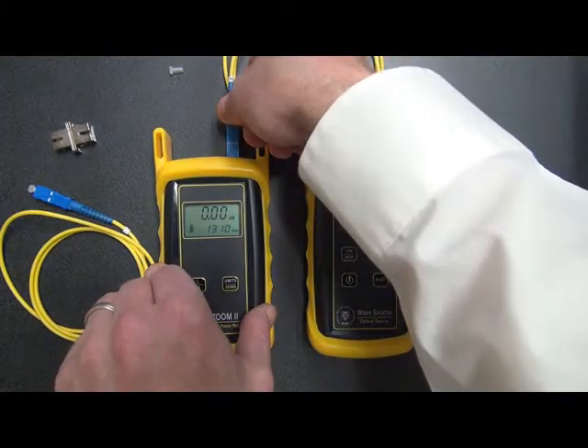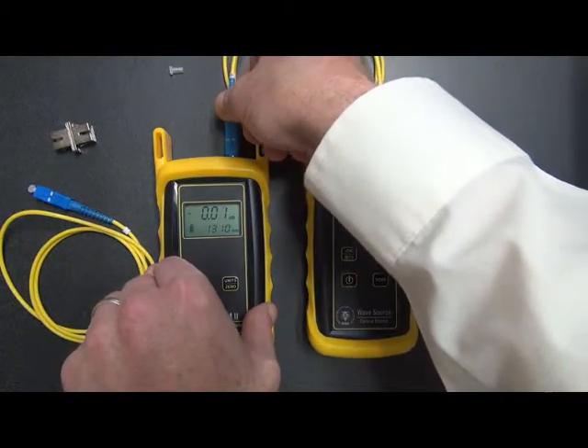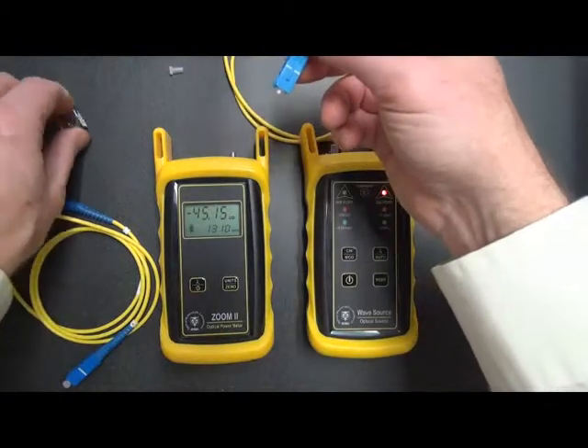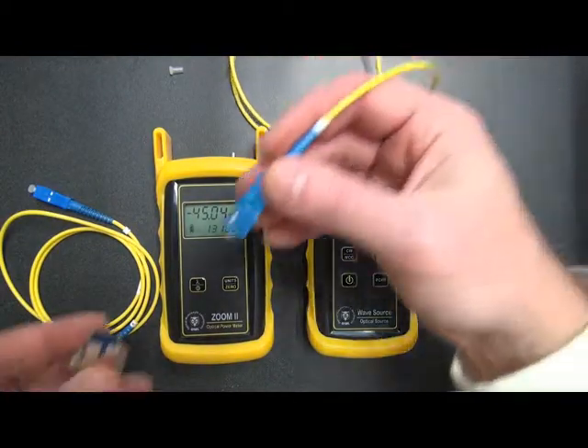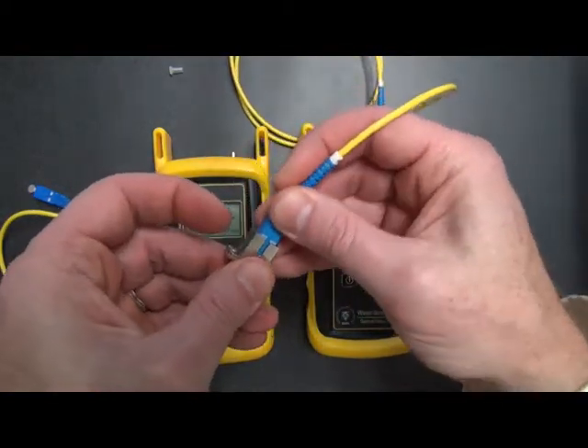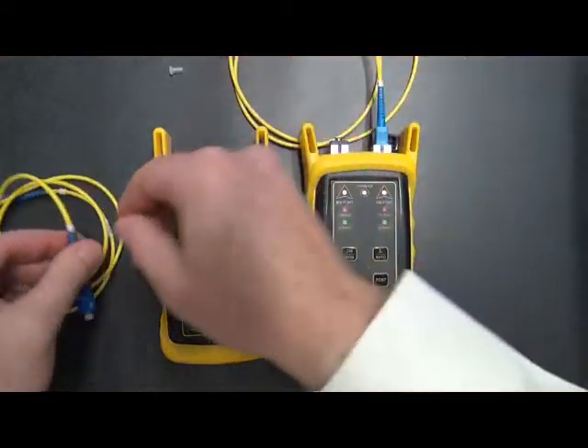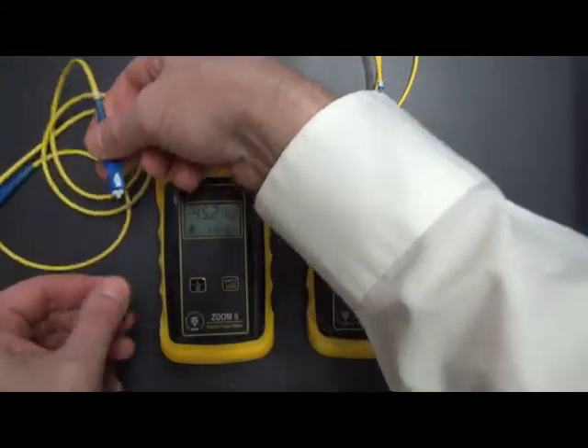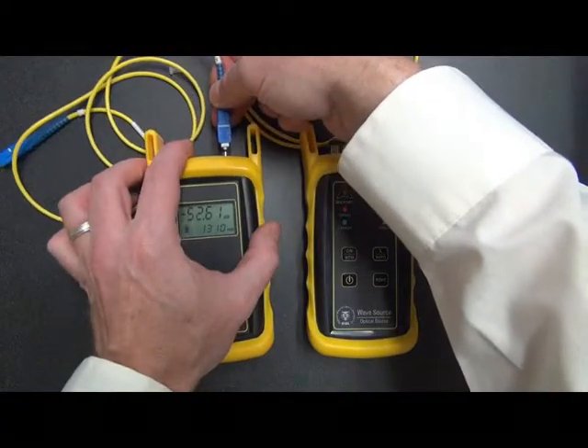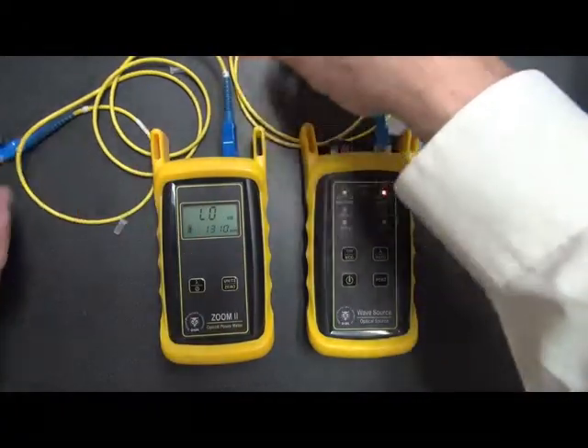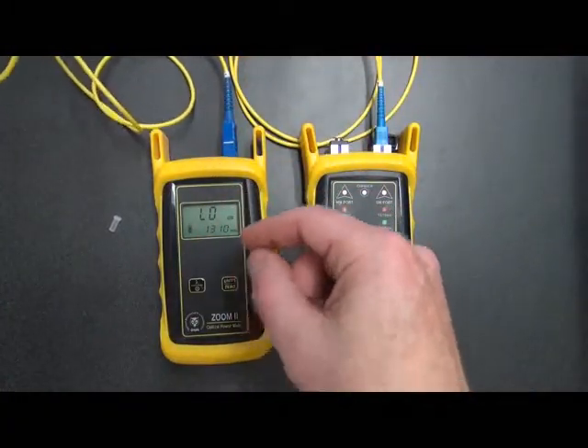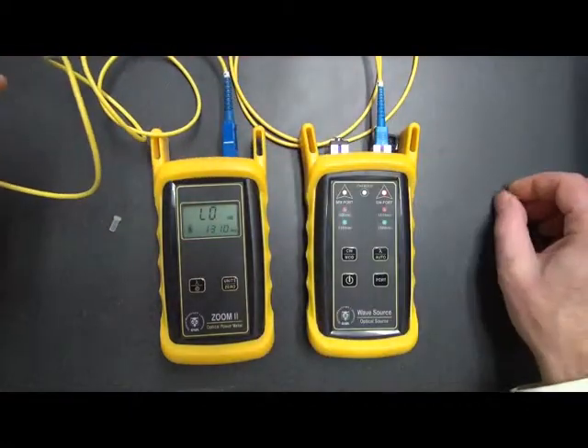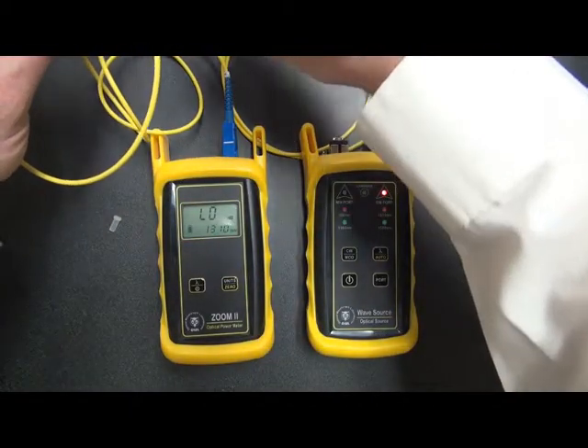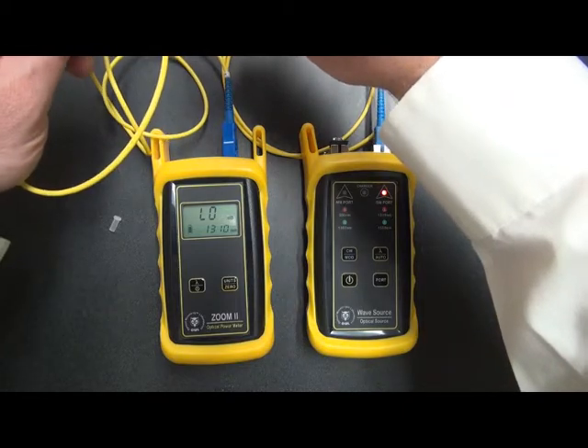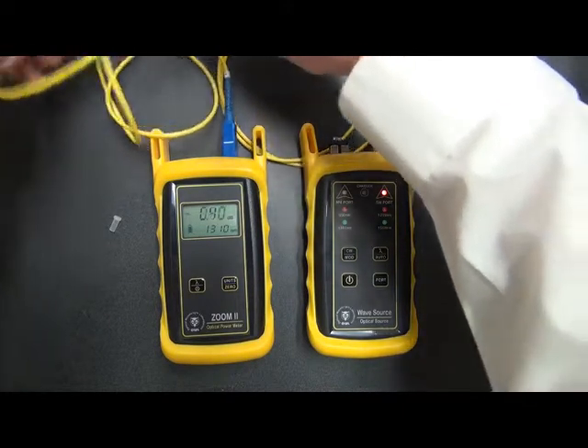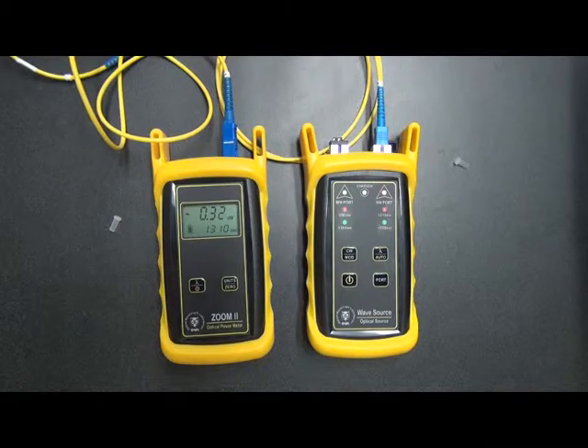To do that, we have to disconnect the reference cable from the detector port, and we'll see that we are reading ambient room light temporarily while we're connecting in this second cable. So we put the mating sleeve on the end of the reference cable. We plug one end of this cable into the detector port, again reading low because there's no light coming into the detector. And finally, connecting this second cable into the mating sleeve and completing the connection.